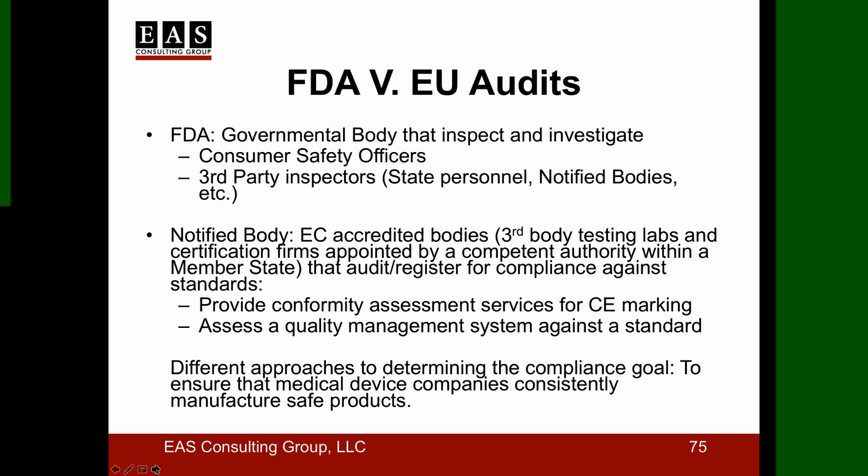Usually with FDA, it's government people, it's consumer safety officers or investigators. Or you're going to have third-party folks like state or notified body or someone like that. The FDA gives a blessing that says, yes, you can be us. So they come in and act like FDA through these different type of third-party programs. On the EU side, there's usually not folks from the European Union, but these outside industry folks called notified bodies or registrars that come in.